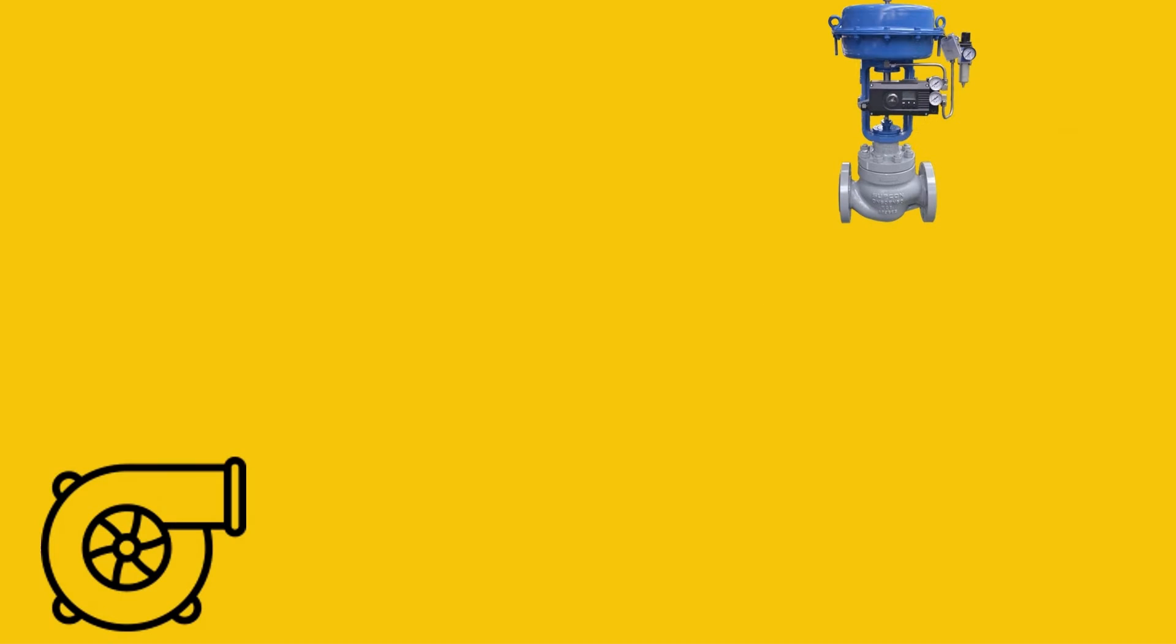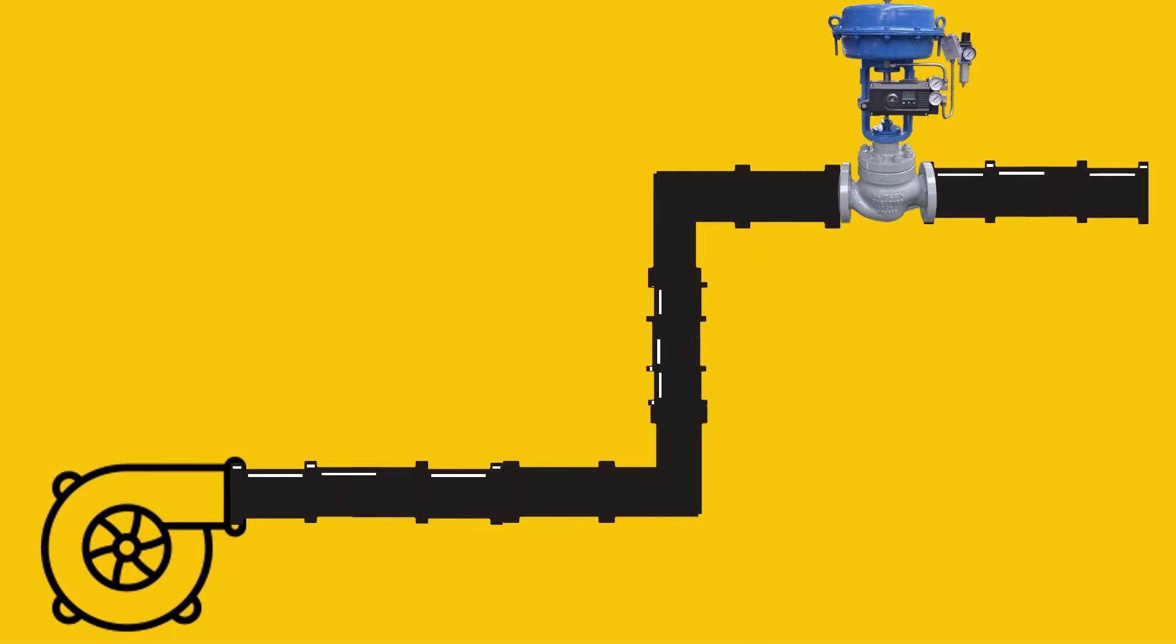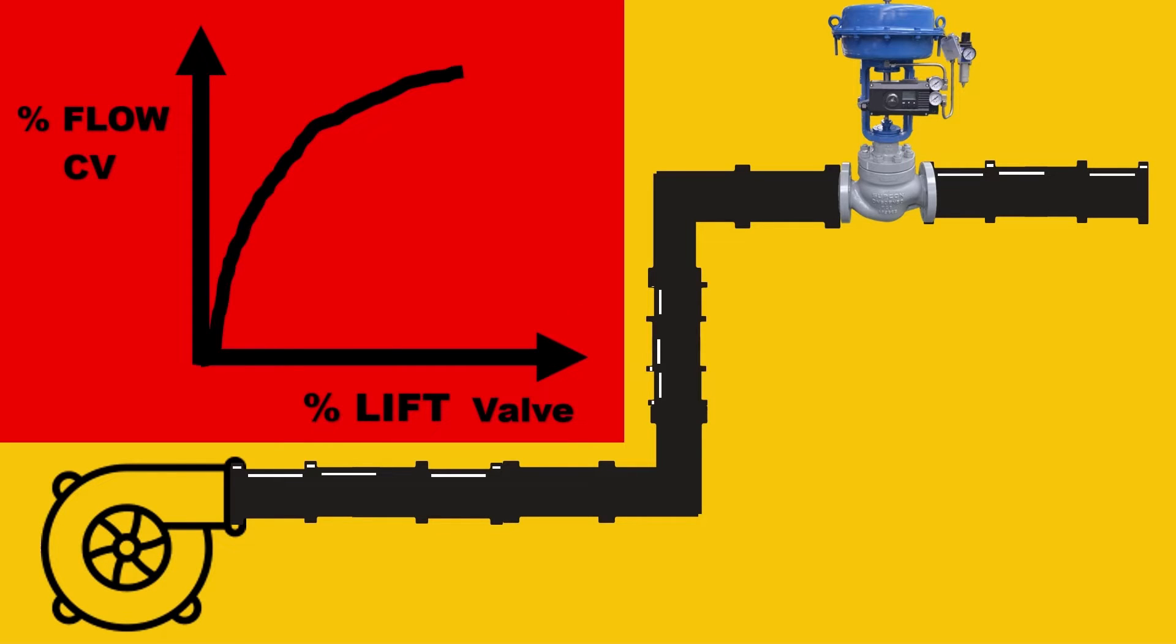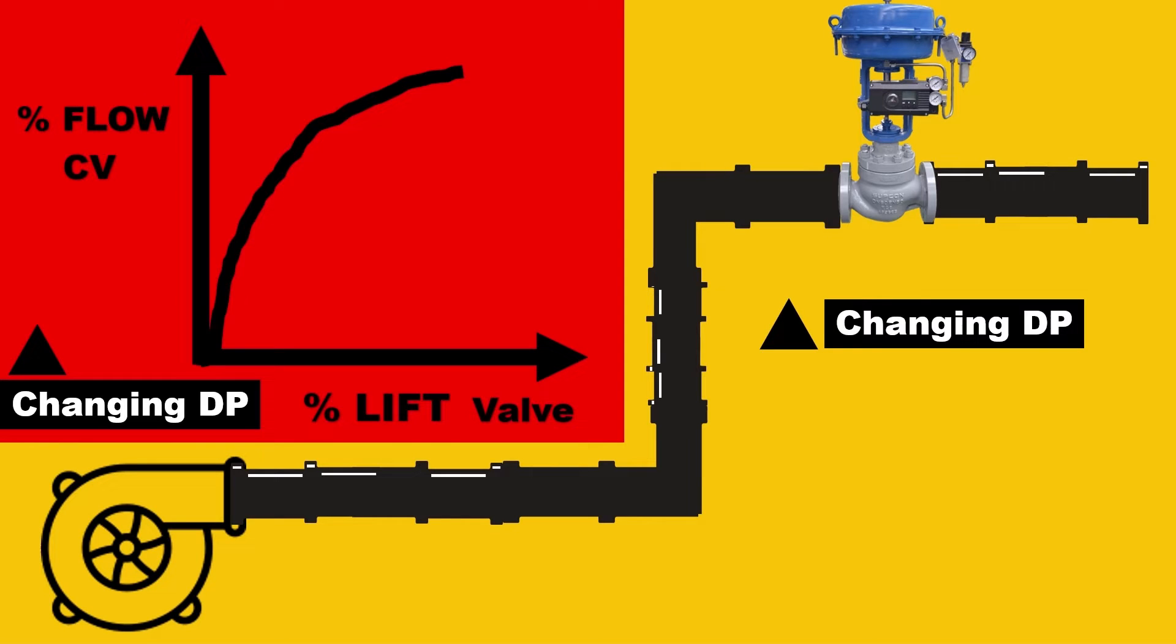Now imagine we put the valve in actual process conditions. What happens here? When we plot lift versus flow CV percentage, surprisingly, it's not a linear curve. Why? Because the DP constantly changes and is not kept constant. This is called installed valve characteristics due to the changing DP.